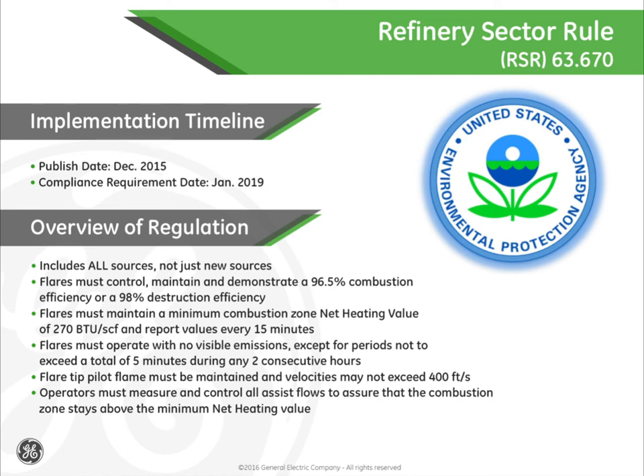Operators must ensure that the combustion is smokeless, which requires certain steam to flare gas ratios. This typically is driven by the makeup of flare gas. Additional steam is not required for gases of molecular weight 16, which is typically methane, and lower, such as hydrogen, but is required for hydrocarbons of C2 and greater.